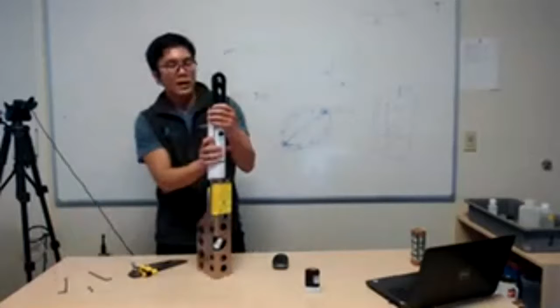The end cap is connected via this little Molex connector right here, so gently remove that. Set this aside in a spot where it's not going to contact any lint, dust, or debris. And then we can see we have the battery pack inside of the instrument.